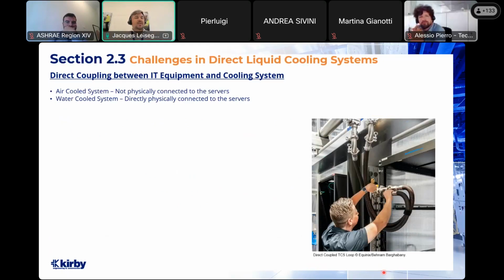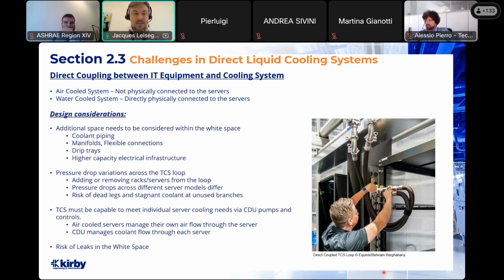The next challenge is the concept of the direct coupling between the IT equipment and the cooling system. So in an air-cooled system, there's no physical connection between the cooling system and the servers. However, in a water-cooled system, it's directly physically connected to the servers. So what does that mean for us? How does that impact how we design and implement these systems? So additional space will need to be considered within the white space. We now have coolant piping, manifolds, flexible connections, drip trays, all serving the liquid cooled load within the white space. So that's all new elements coming into the white space, and space needs to be considered for that.